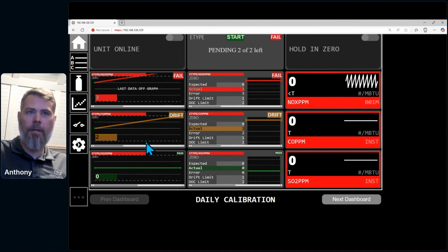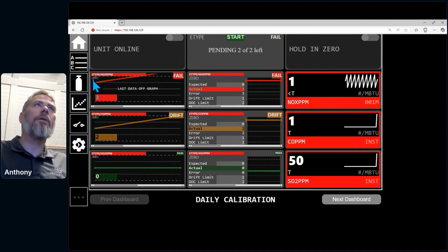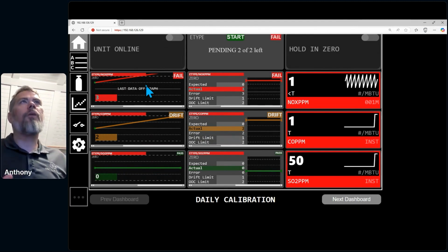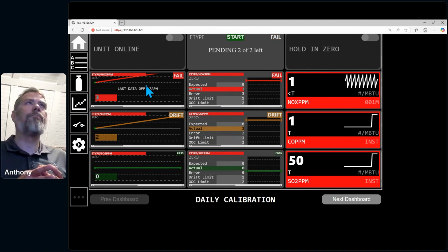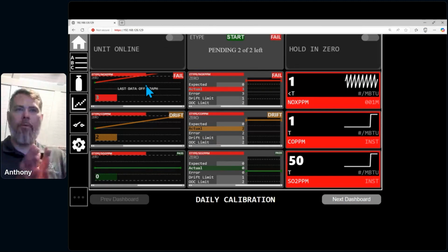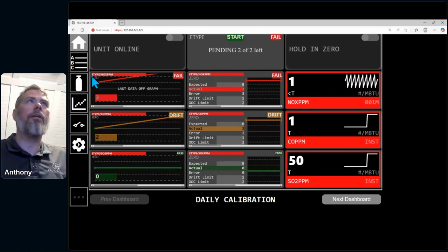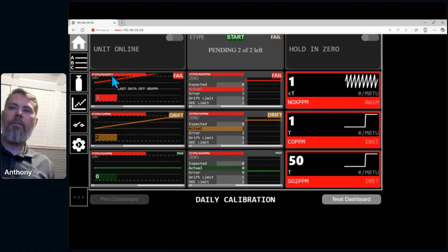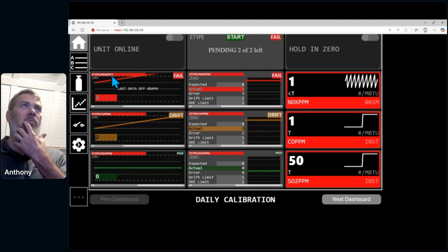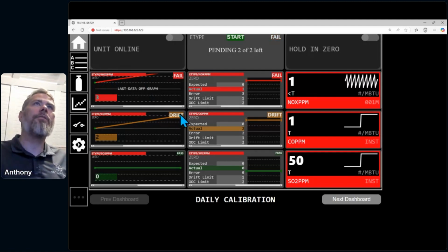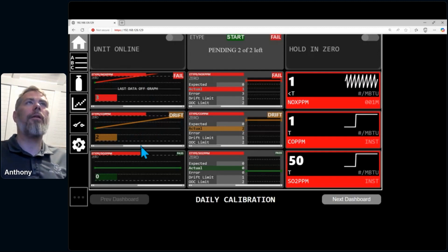So we've got the calibration and the channel in the top left. The current phase is displayed just below that. And the calibration is not running right now, so I'm looking at a historical view, and what it's showing me is the last run of the 0 phase for this particular channel. Now, the background color of the calibration and channel, you can see it's red here. That indicates the worst status of all phases for that channel in that calibration. So you can see here that this particular phase and channel drifted in this 0 phase, but it's red, which means somewhere it failed.